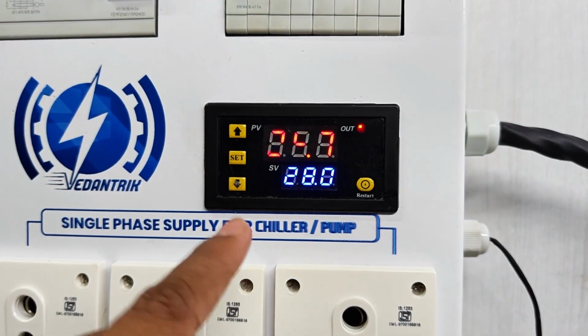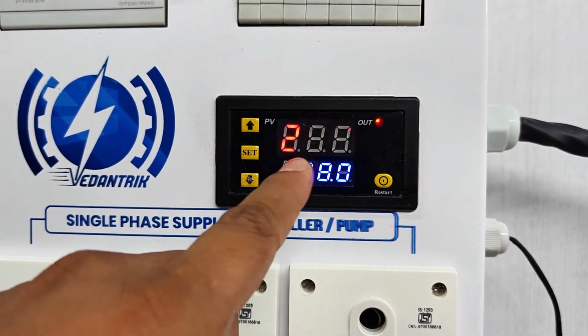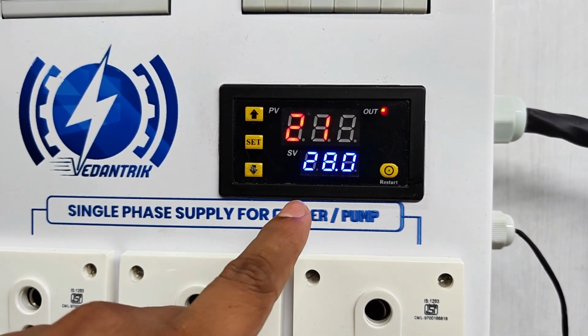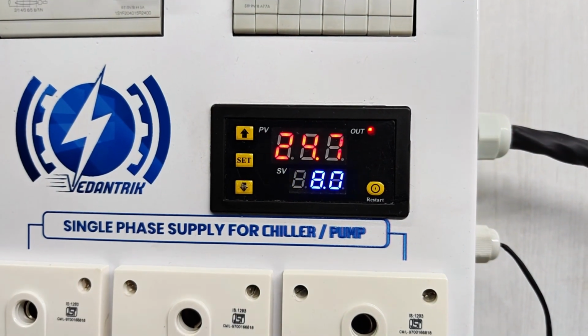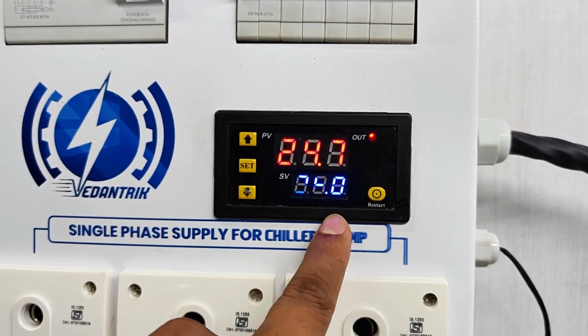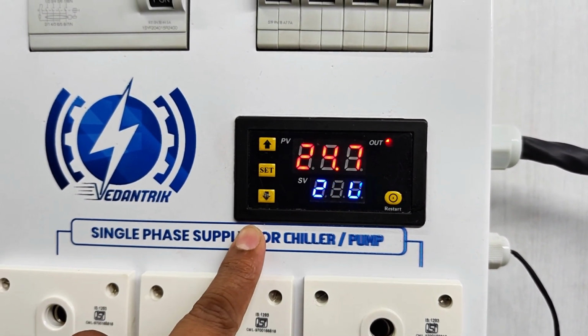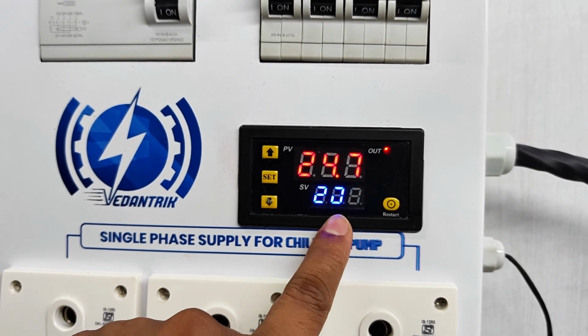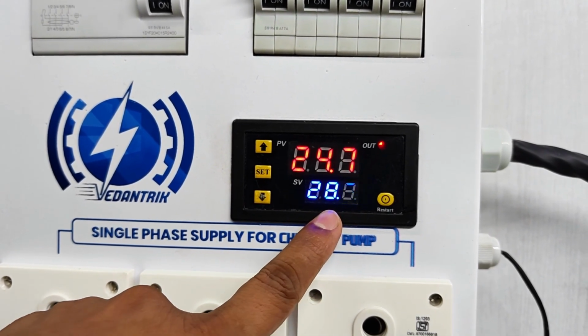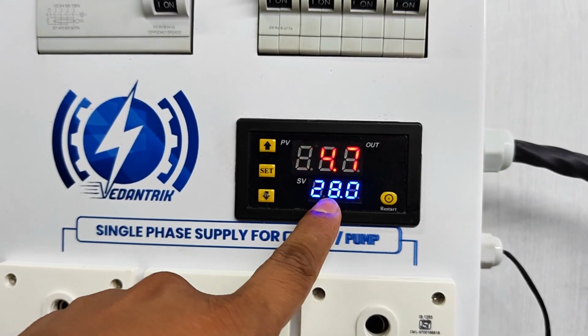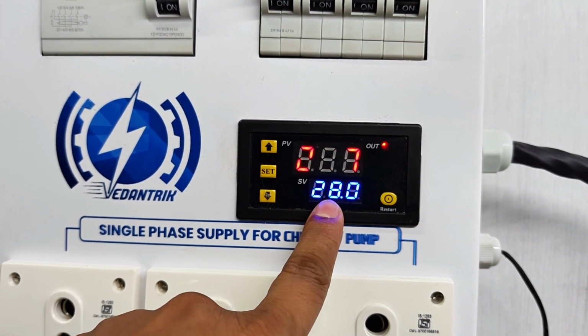But note that whatever temperature you are setting, suppose you set 27 degrees Celsius, it will cut off at 25 degrees Celsius. Suppose you set it as 29, it will still cut off at 25 degrees Celsius. So always keep this set value as 27, because as per the code, the set value should always be 27 plus minus 2. So that's why always keep this set value at 27.